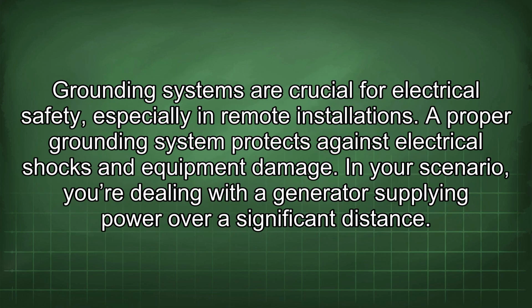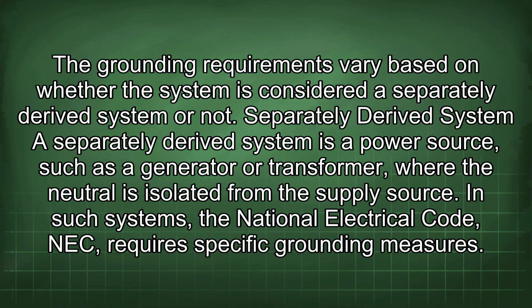Grounding systems are crucial for electrical safety, especially in remote installations. A proper grounding system protects against electrical shocks and equipment damage. In your scenario, you're dealing with a generator supplying power over a significant distance. The grounding requirements vary based on whether the system is considered a separately derived system or not. Separately derived system: a separately derived system is a power source, such as a generator or transformer, where the neutral is isolated from the supply source.